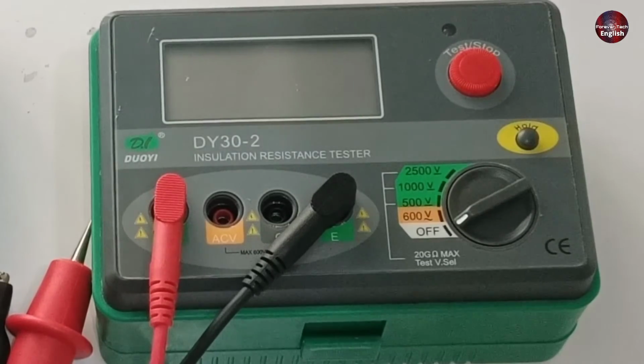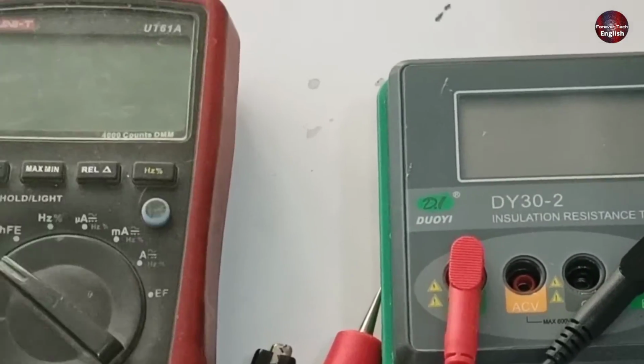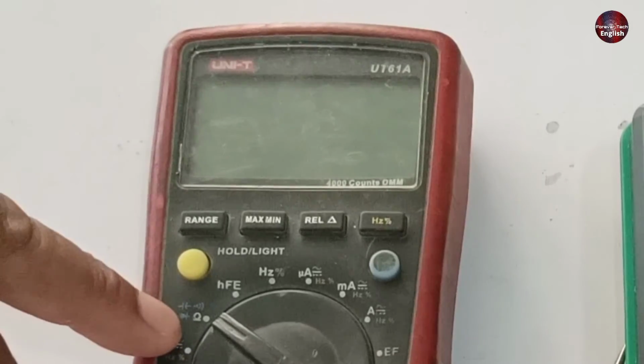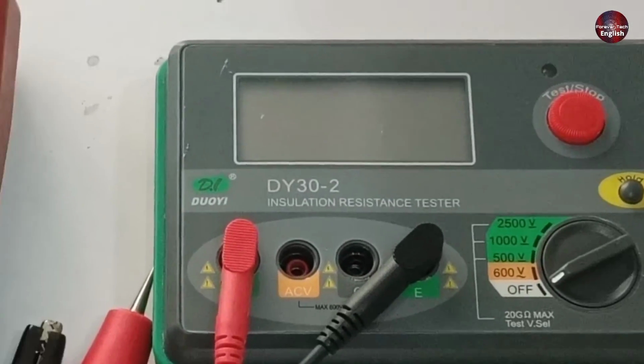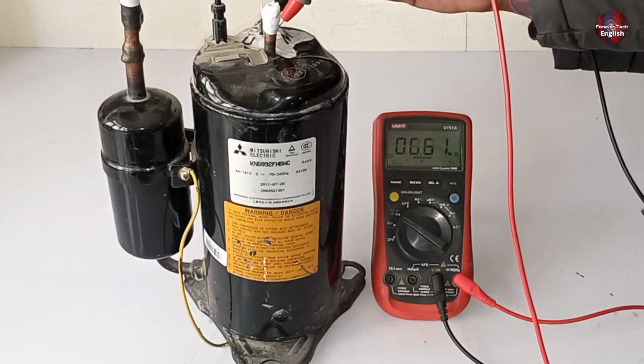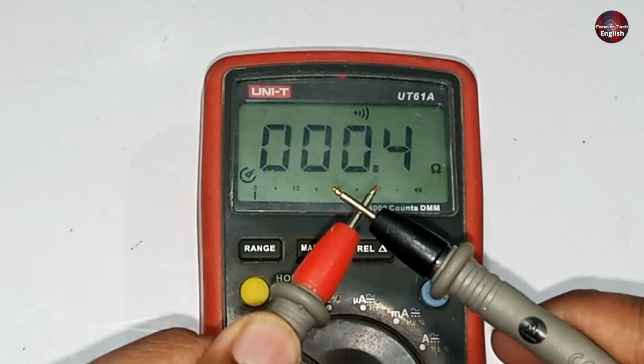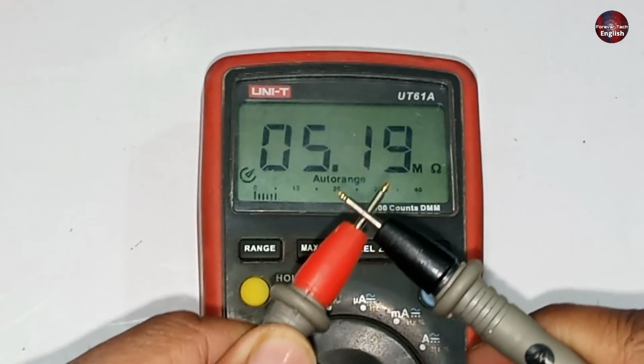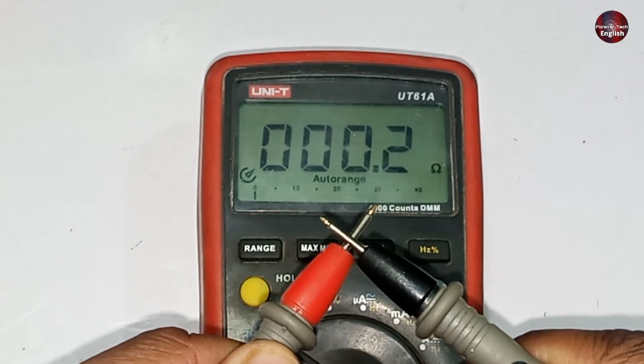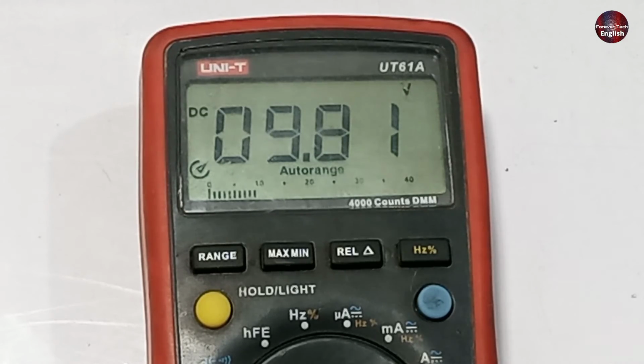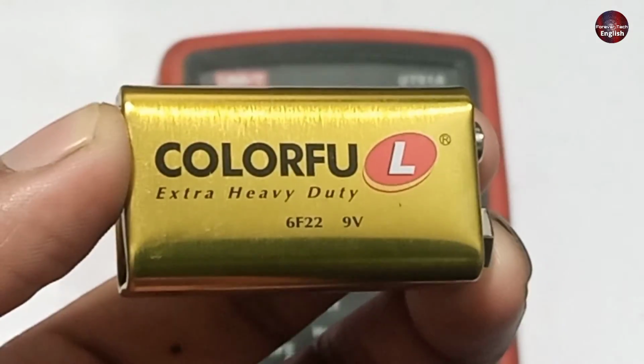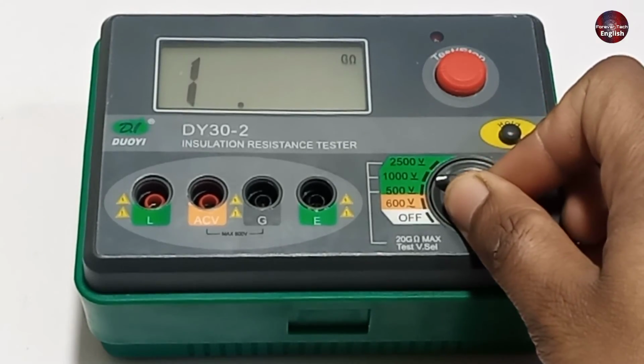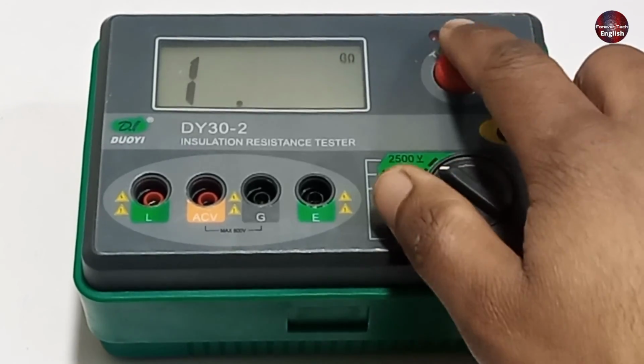Now, at last, let's talk about why we need an insulation resistance tester, as it can be tested with a multimeter. The megger has its own value, and the multimeter has its own. But when we check the compressor with the multimeter, we check it on continuity and ohm mode. If we check it through a multimeter, it will only pass 9 volts through the device we are testing as it has a 9-volt battery inside it. But the insulation tester will provide 500 to 2500 volts.